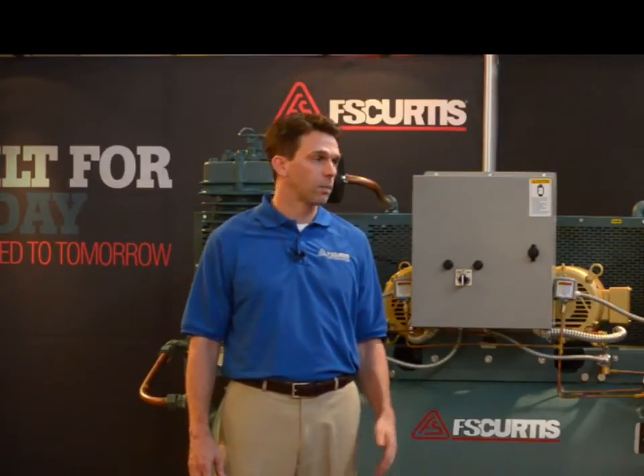Thanks, Matt. There are many great advantages to rotary screw air compressors. This is not a new technology to be intimidated by — rotary screw compressors have been around for decades and just recently have they become more affordable for the average shop owner. Rotary screw compressors can run 100% continuous duty — 24 hours a day, 7 days a week, 365 days a year. They also provide clean, dry air with less than 3 parts per million oil carryover, which is great for painting applications and other critical air quality applications.